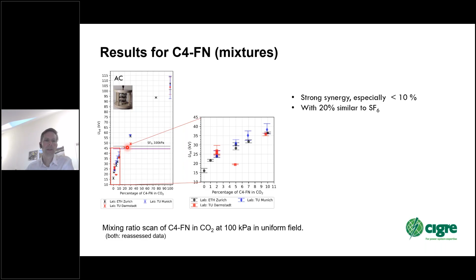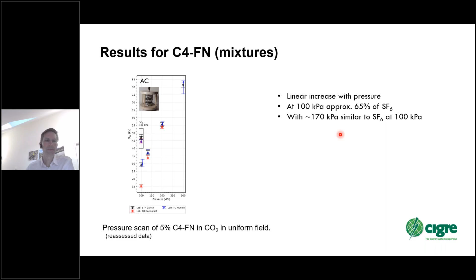We also did a pressure scan at a fixed percentage, so at 5%. And you can see there's a pretty linear increase with pressure, as we would expect. And at 1 bar, the strength of this 5% mixture is approximately 2/3 of the strength of SF6 under uniform configuration. And with 70% overpressure, you reach a similar electric strength level to SF6 at 1 bar.